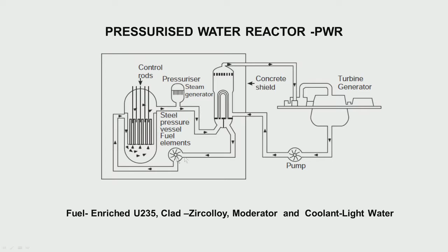Whereas in a boiling water reactor, steam is produced here, and it is not a fully saturated steam. And you cannot send steam mixed with water to the turbine. So, you have moisture separators at the top of the reactor, and then only the steam is sent here. Since the moisture separators are here, it puts an obstruction for the control rods. So, the control rods are pushed from the bottom. Control rods in a boiling water reactor come from the bottom. This is the difference between the two.